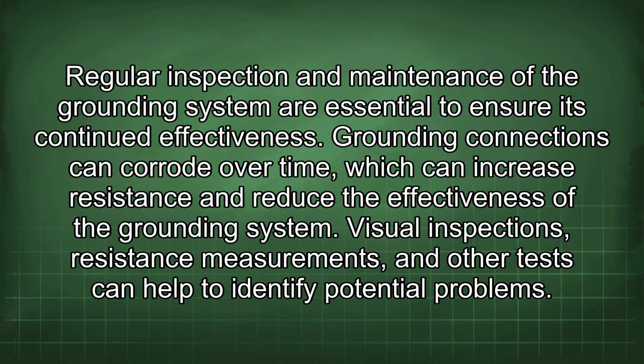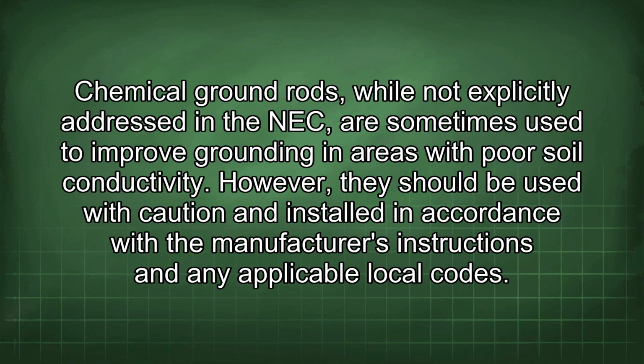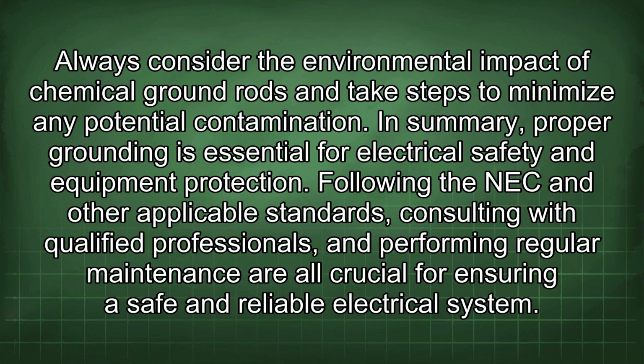Regular inspection and maintenance of the grounding system are essential to ensure its continued effectiveness. Grounding connections can corrode over time, which can increase resistance and reduce the effectiveness of the grounding system. Visual inspections, resistance measurements, and other tests can help to identify potential problems. Chemical ground rods, while not explicitly addressed in the NEC, are sometimes used to improve grounding in areas with poor soil conductivity. However, they should be used with caution and installed in accordance with the manufacturer's instructions and any applicable local codes. Always consider the environmental impact of chemical ground rods and take steps to minimize any potential contamination.